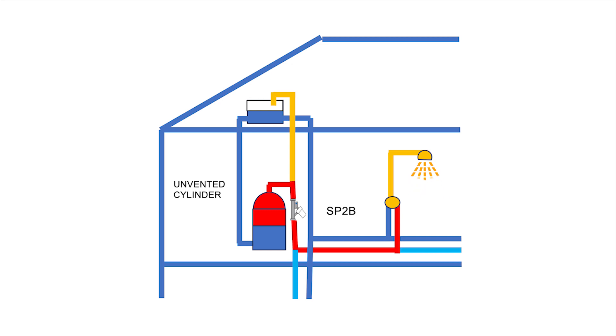If your cold pressure is also low, you need an SP22S to single boost the hot and single boost the cold. For gravity hot and mains pressure cold, the better solution is to double boost the hot only with an SP21S.